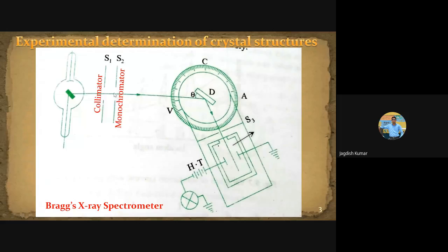And what will happen? That set of planes will specify the diffraction condition for various wavelengths at various angles. So what we do is we arrange our setup in such a way that the peak which corresponds to the highest intensity is taken out for the measurement further. So in your output, you have only that specific wavelength at that specific angle which we desire to use. So the monochromator itself employs Bragg's law of X-ray diffraction.